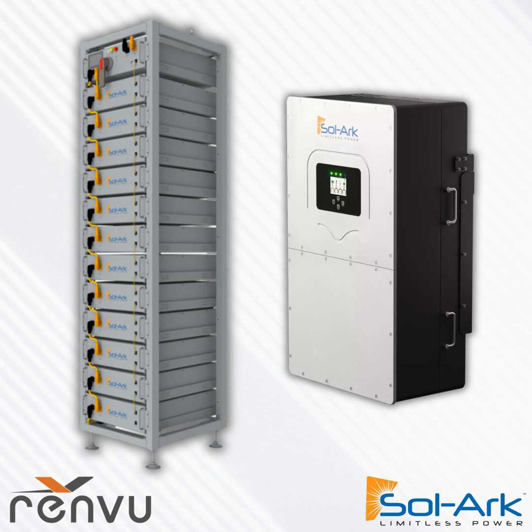To round this presentation off, you can go into the line side or grid side of the service, and do whole building backup with Sol-Ark. We've been doing 2000 amp service, grid pass-through, even with three-phase, going back to our residential product line, even before we had a commercial three-phase out-of-the-box product line for 208 or 480. So we have experience with parallel inverters, and there's a lot of technical reason why we can do parallel inverters better than anyone. We have oversized grid relays built into each inverter, which helps not just with single inverter installation, but for parallel inverter grid seamless transfer.